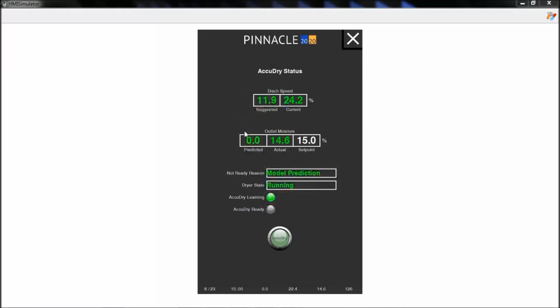It tells you what the current discharge speed is, as well as what the AccuDry board thinks the current discharge speed should be. It also tells you what the actual outgoing moisture is, as opposed to what it's currently predicting. You can see in our simulation, where we've been changing numbers in a way that doesn't exactly reflect reality, the board's having trouble predicting what the current output moisture should be.